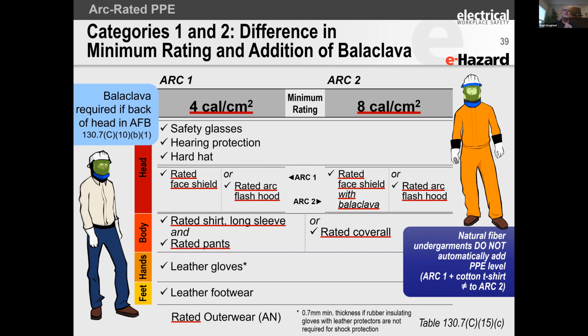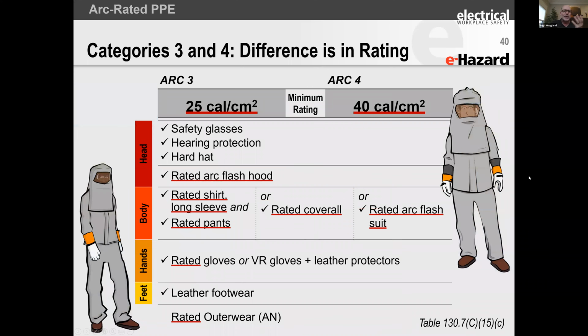In the US, we use arc categories, or CAT, or HRC—I think was the old terminology. I like to call them ARC, but most people are calling them categories now. It's called the PPE categories. 4, 8, 12, or 4, 8, 25, and 40 are the most common, and that's in a standard called NFPA 70E, which is used around the world somewhat because of US multinationals.